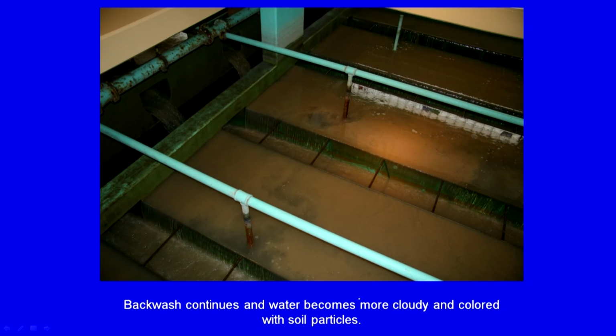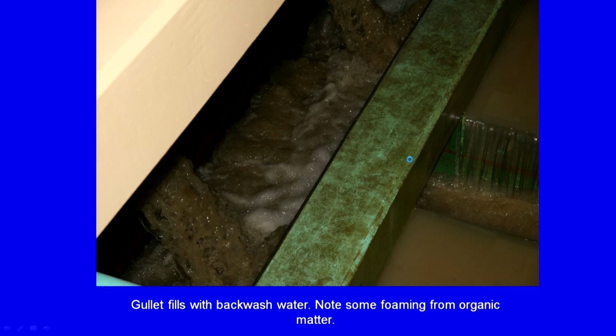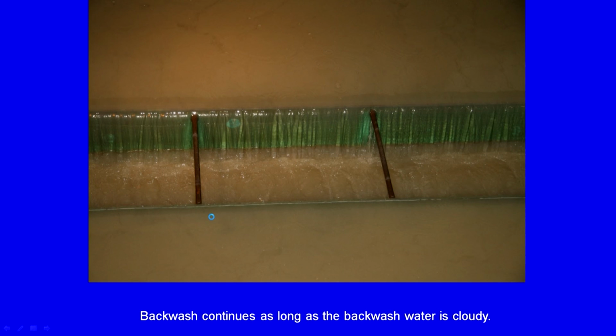Backwash continues and water becomes cloudy and colored with soil particles. So, that is what you see here, and then it is going to be collected in your backwash troughs. We also see foaming from organic matter, and the backwash water now is relatively clouded, or pretty poor in quality.